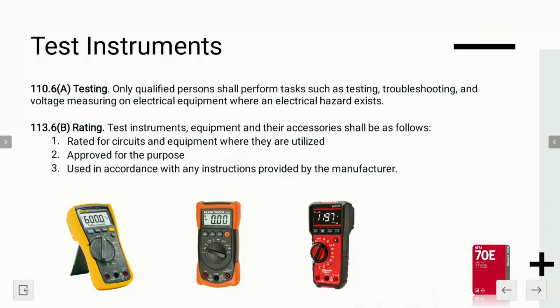The 70E also says that our test instruments, equipment, and their accessories shall be designed for the environment to which they're exposed and the manner they're going to be utilized. It says test instruments and equipment and all associated test leads, cables, power cords, probes, connectors have to be visually inspected by the qualified person for any defects or any evidence of damage that might expose that qualified person to an injury. And if it is defective, we have to take it out of service and have it fixed, repaired by somebody that's qualified to fix or repair our meters.